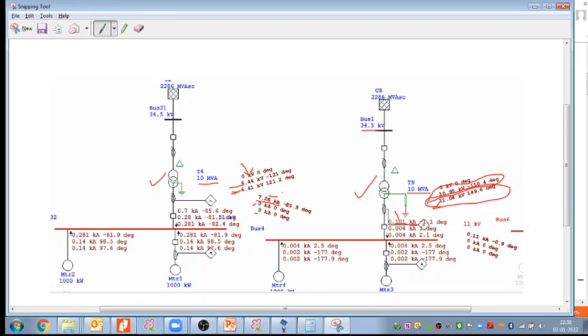So whenever we have a rotating machine, we cannot allow this much short circuit current, in order to protect the core and the core insulation. In that case, it is mandatory to use the NGR. Point number one is this.